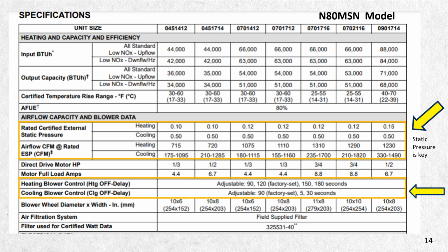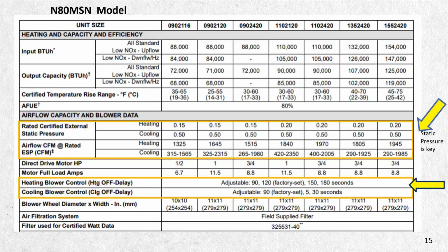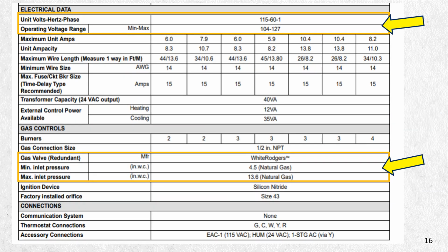But also keep this in mind about your static pressure on that model. On this model, as you get bigger, the heating static pressure on the heat side is a little bigger, but cooling is staying the same. So keep that in mind. You have to be 0.50 or lower in the cooling setting as well.